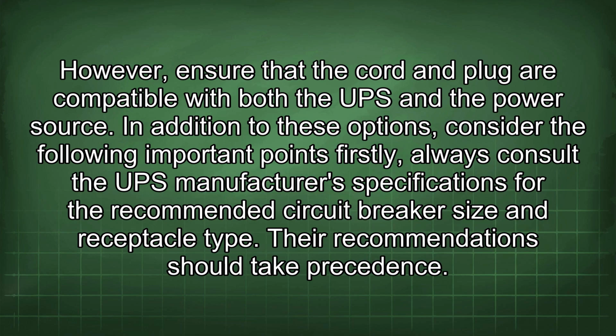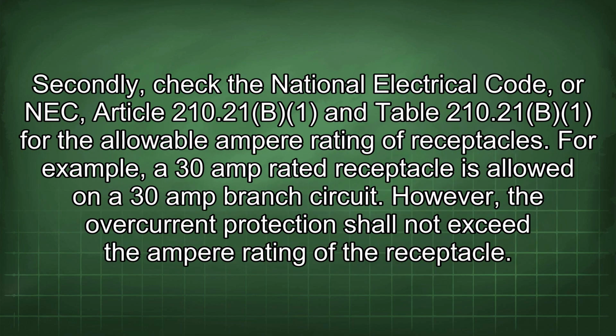In addition to these options, consider the following important points. Firstly, always consult the UPS manufacturer's specifications for the recommended circuit breaker size and receptacle type. The recommendations should take precedence. Secondly, check the National Electrical Code, or NEC, Article 210.21(B) and Table 210.21(B) for the allowable ampere rating of receptacles. For example, a 30 amp rated receptacle is allowed on a 30 amp branch circuit. However, the overcurrent protection shall not exceed the ampere rating of the receptacle.